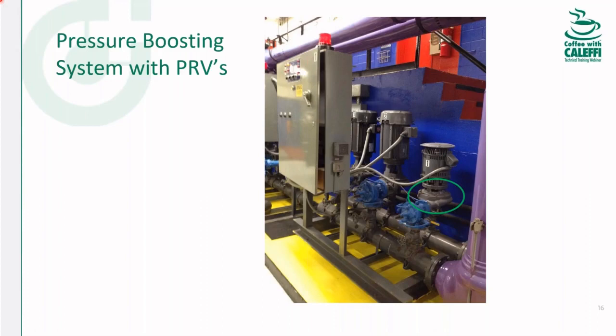I don't know, Reece, when's the last time you saw a system using a jockey pump? Well, I usually see these in existing installations because that's what they did years ago. If you go with the old way of doing things, they'll have what they call a 20-40-40, a 20% pump and then two 40% pumps. And the smaller pump was running to take care of the low loads, but they all still had fixed speed motors and regulator valves. And then the only other time I see it today on modern systems is a jockey pump for a fire system. Right. Just if there's a small leak in the system, you don't want the big pumps coming on to get the pressure back up. That would be bad. So, okay.